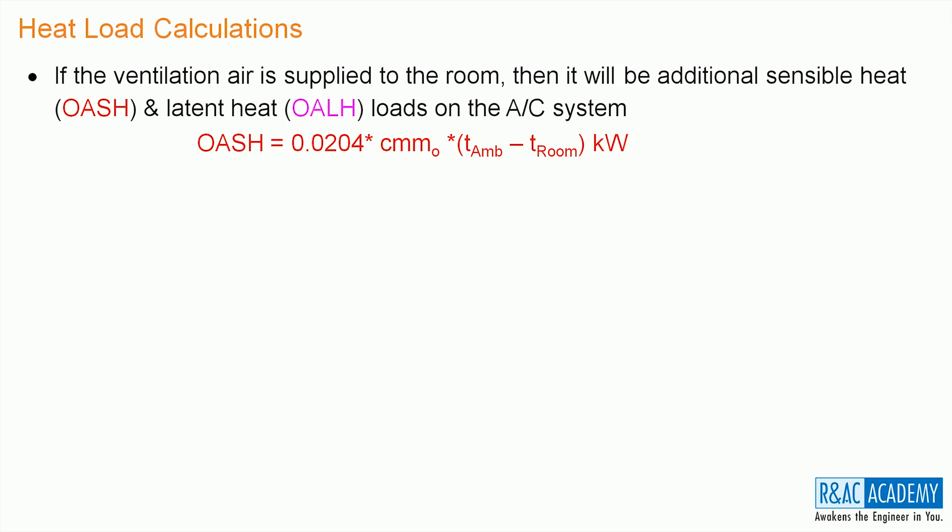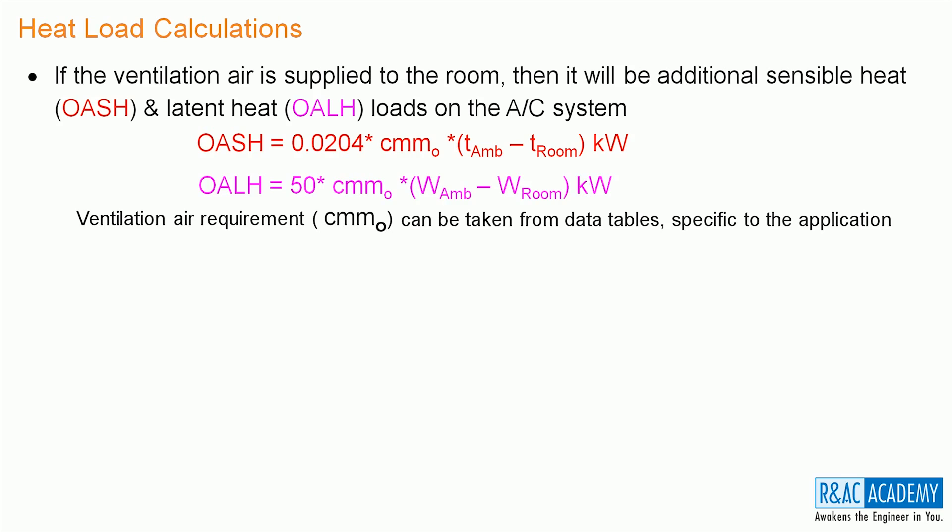What is CMMO? It is the ventilation air required for that specific application and it can be had from the data table specific to that application. Similarly, OALH can be computed using this formula: 50 times CMMO times specific humidity of the ambient air minus specific humidity of the room air.